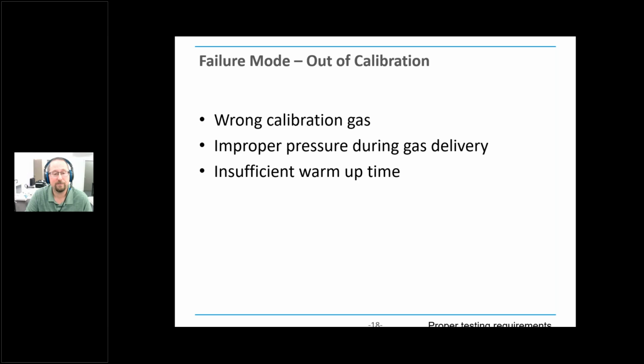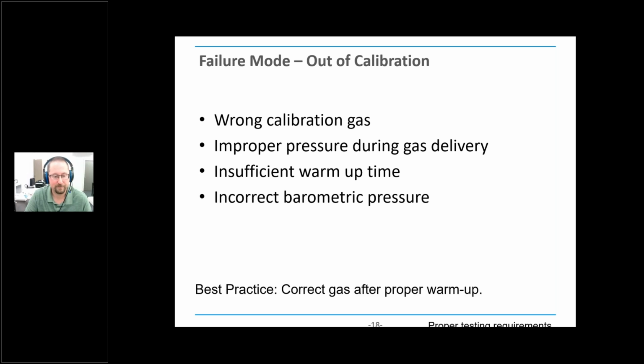Not waiting long enough for warm-up time. That's not to make your life inconvenient. It really does need warm-up time, because the way those sensors work, they have to warm up in order to be accurate. And so when it says wait 20 minutes, they really do need you to wait 20 minutes if you're trying to calibrate it. And then again, we talked about using the wrong barometric pressure. So of course, best practice, make sure you use the right gas, let it warm up, make sure you deliver the gas properly.